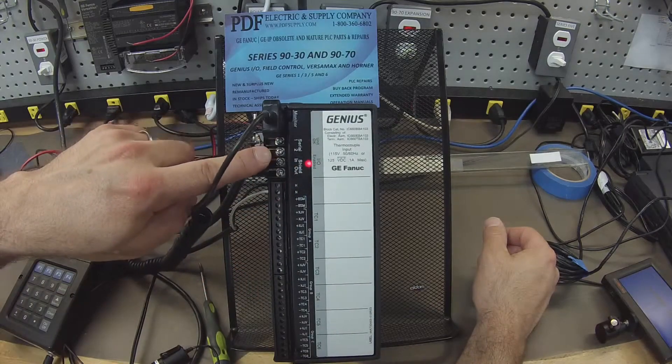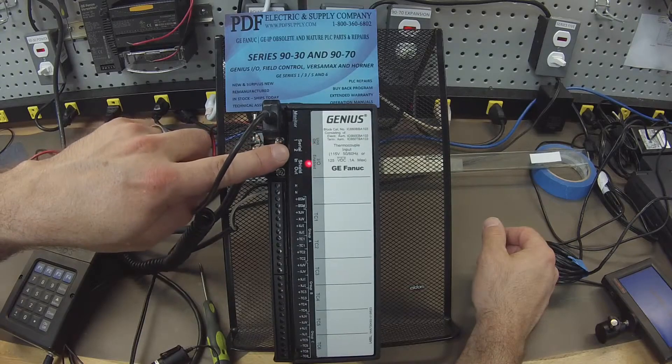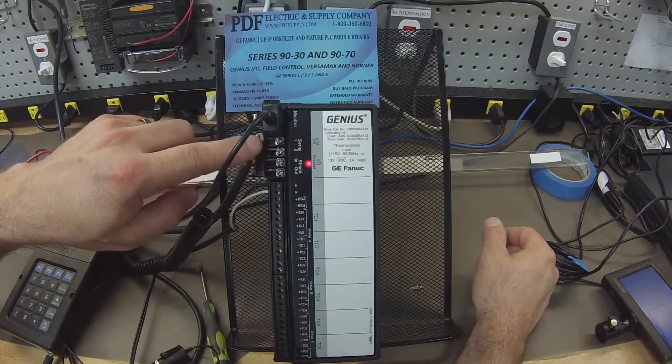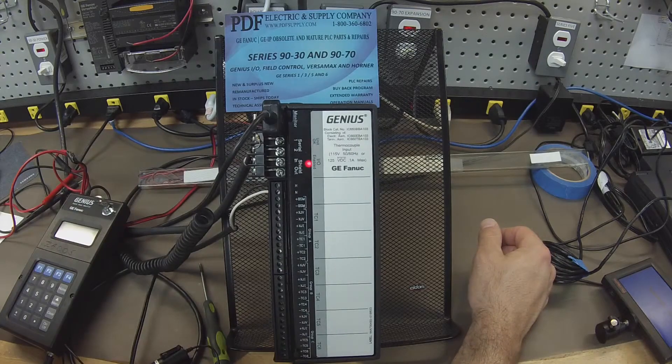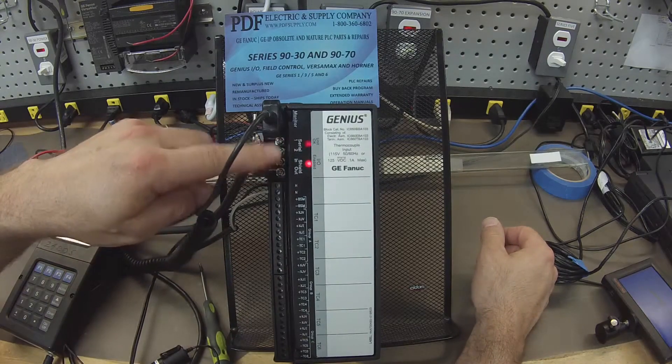That tells me that the serial port—this is coming through Serial 1, Serial 2, and shield in and out, and going back and forth to the Genius bus controller—is communicating and that this port is working good.